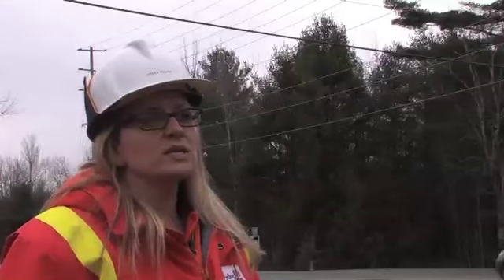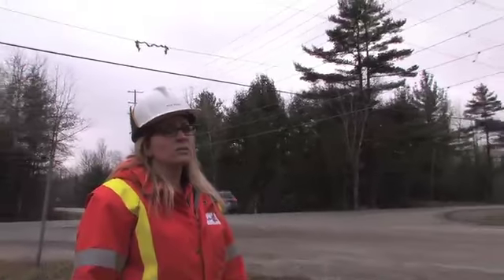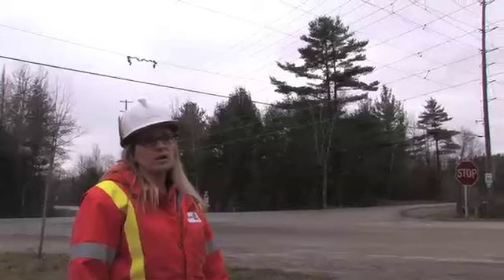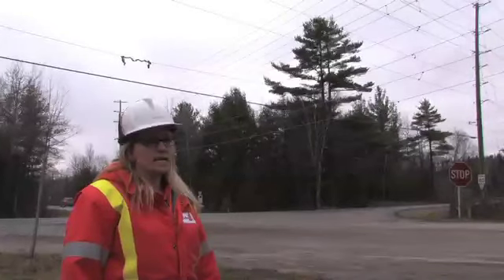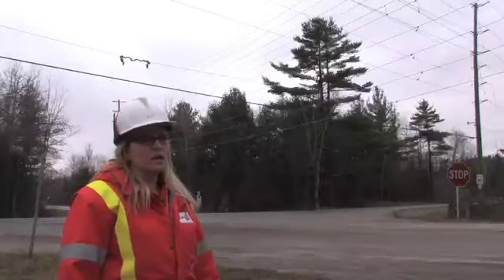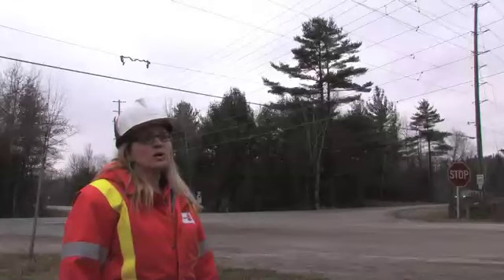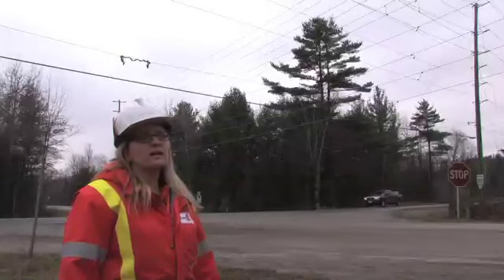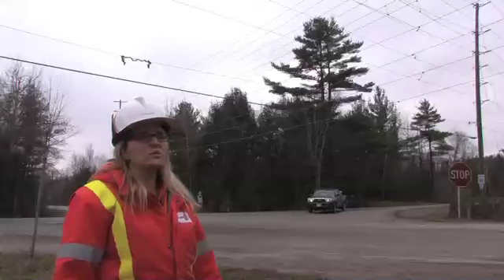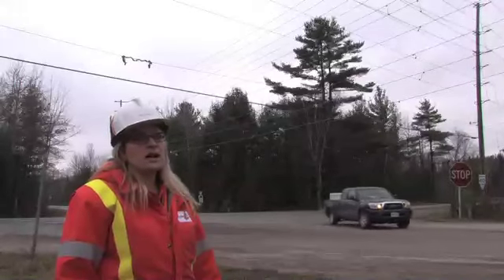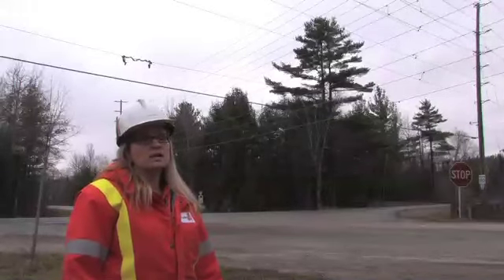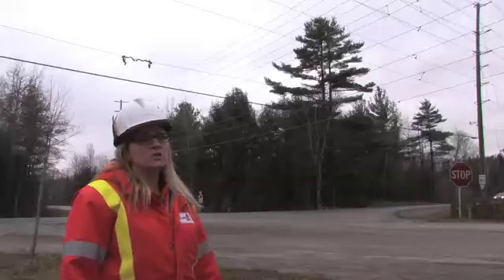Right now you'll see a tower crossing where we have one 44 circuit and one underbuild circuit going underneath the tower line on crossarms. We now need to get a second 44 circuit on those poles. So we go to Technical Services and they're helping us with span length, with clearances, and just a standard period, because our standard book does not show two 44 circuits on crossarms.